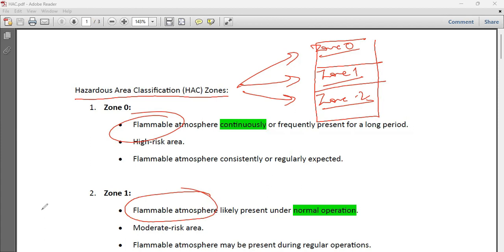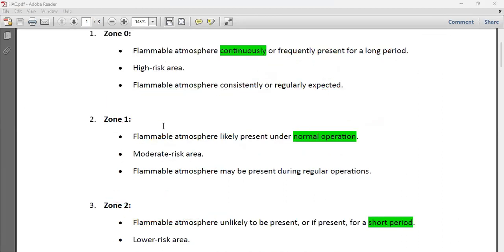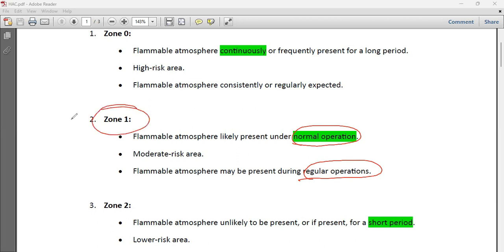Zone 0 means the flammable atmosphere is continuously or frequently present — it is always there for a long period of time. That means Zone 0 is a highly risky area. For example, inside a hydrocarbon storage tank, the flammable atmosphere is always present, so that is Zone 0 — continuous hazardous atmosphere.